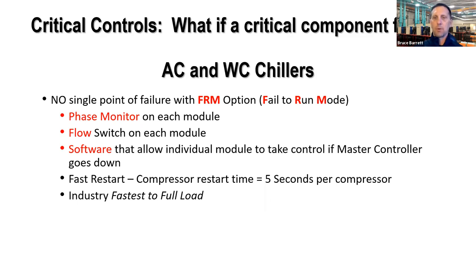We've got accessory controls on there such that if your master controller goes down, the slave controllers take over making chilled water out of each individual module. This FRM option also has a phase monitor on every module and a flow switch on every module. So if one of those components fails, it's not going to take the entire chiller down. We also have very fast restart time with our scroll compressors. We can load up a compressor every 5 seconds. So it's simply doing the math: 10 compressors, one every 5 seconds, 50 seconds to full load. Very, very fast restart time.